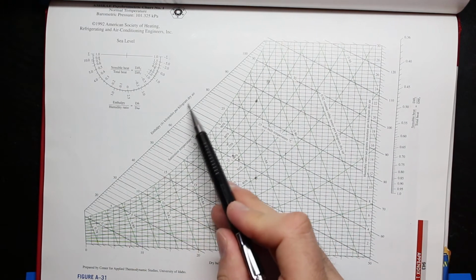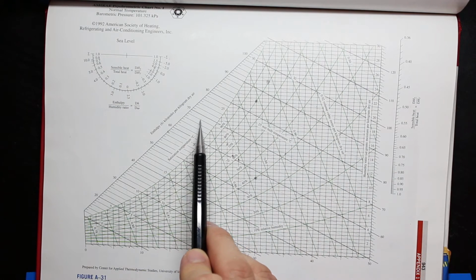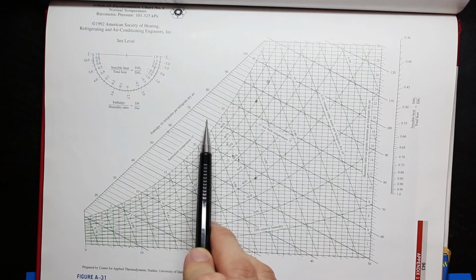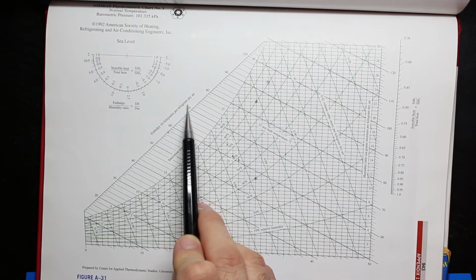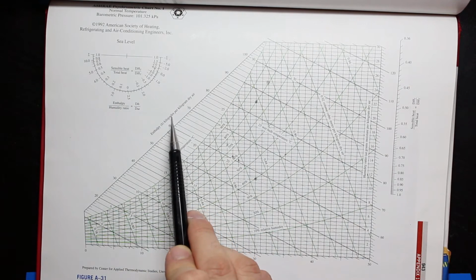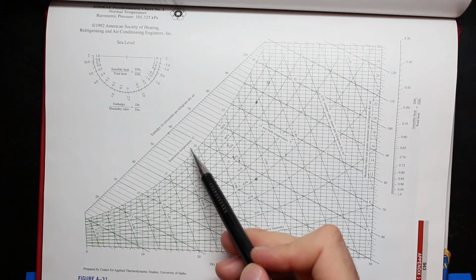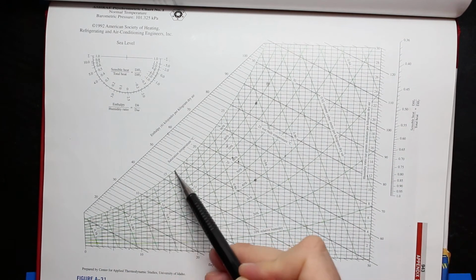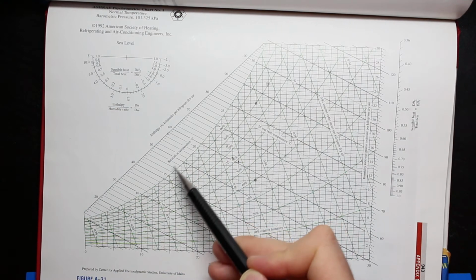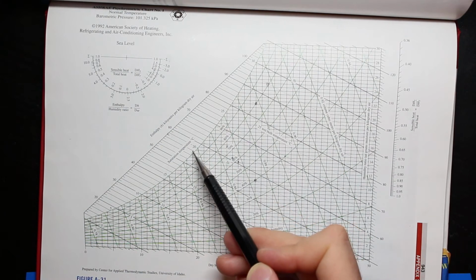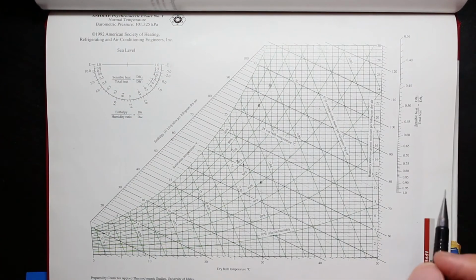These are the enthalpies. So the enthalpy lines are shown with solid lines. You see this solid line? This is the enthalpy of 70 kilojoule per kilogram dry air. The unit is very important. 70 kilojoule per kilogram dry air, then 80, 90. These things here are the saturation temperature. I will discuss that later, but basically the temperatures that we see here are the dew point temperature. I will discuss that specifically for dew point.